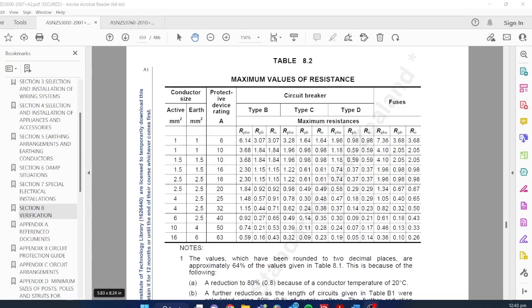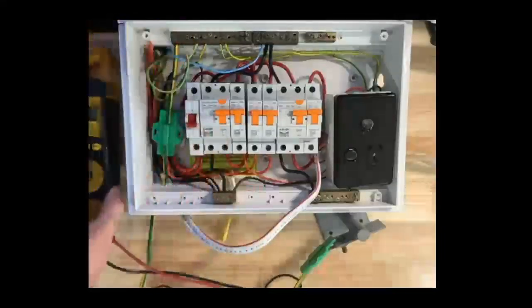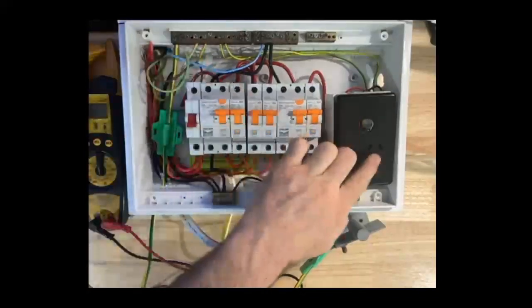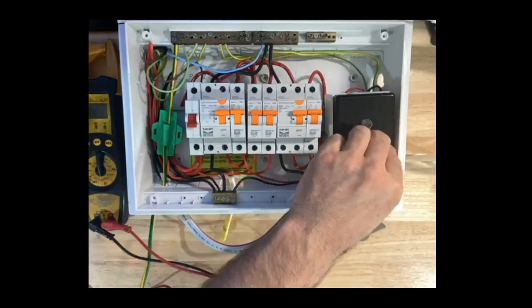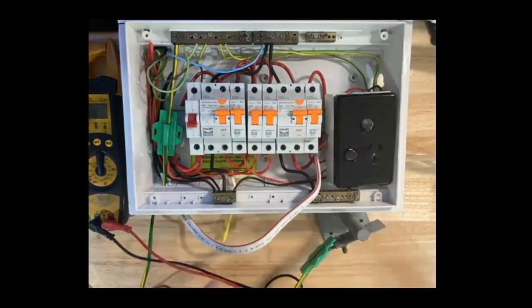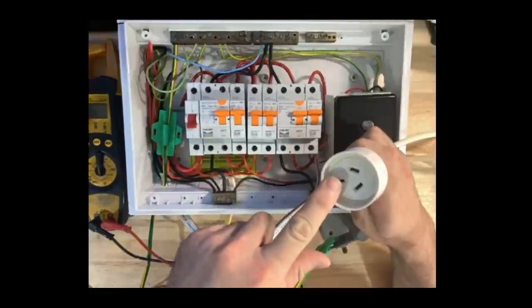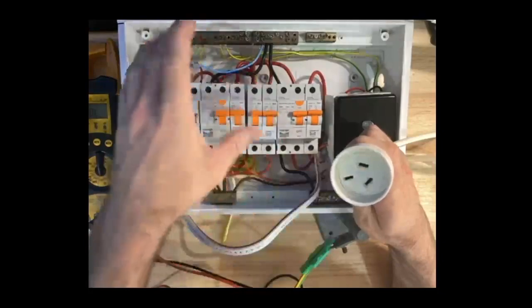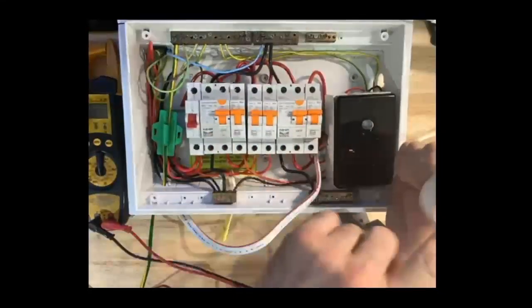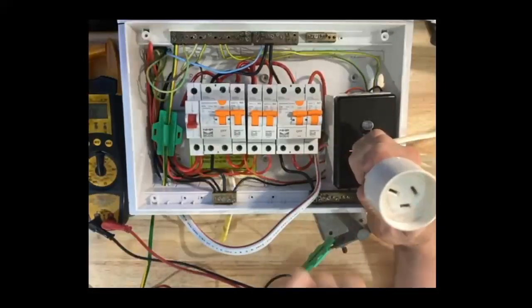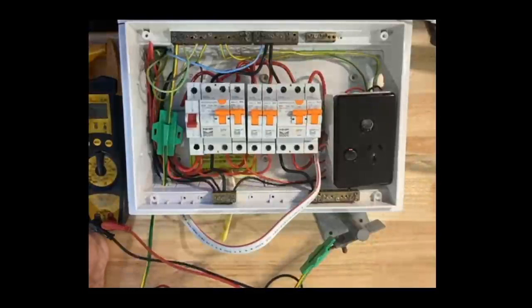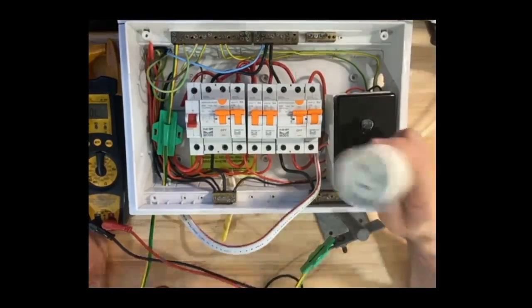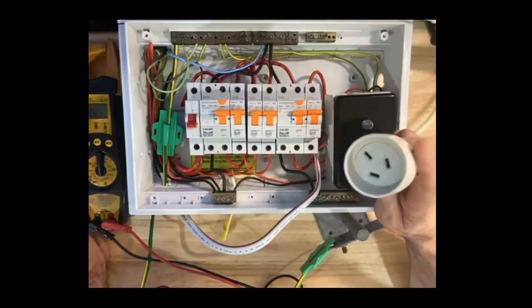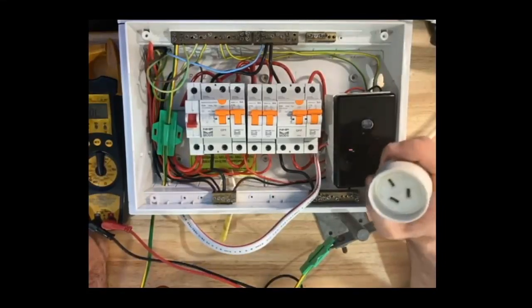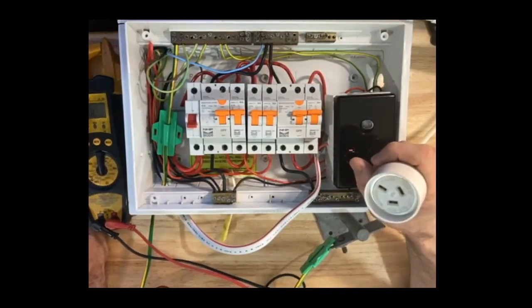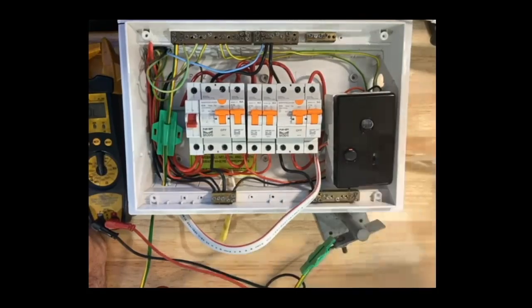Another way to do that test, if you did not want to put the link in between the phase and earth, is if I'm just testing sockets, I could put an extension lead in here, run that extension lead back to my switchboard, and then test between the earth socket on my extension lead to the earth busbar. That would tell me the resistance of the earth wire for my subcircuit, but also the earth wire for my extension lead. So I'm going to add that resistance on there. And if both of those resistances combined are still less than 0.49, then I know that's good. But you are going to add quite a bit of extra resistance by adding in the earth conductor of your extension lead. So that may not be the best way to do it. It just depends on what your situation is and what sort of results you are seeing.